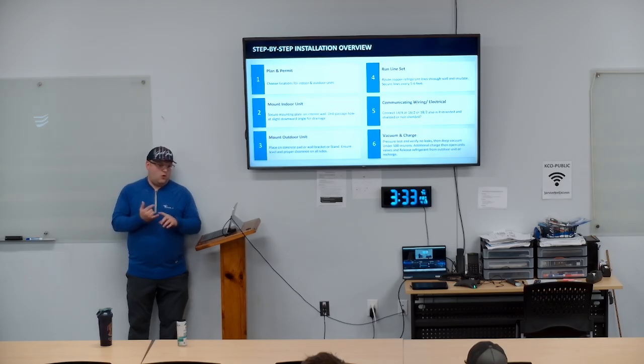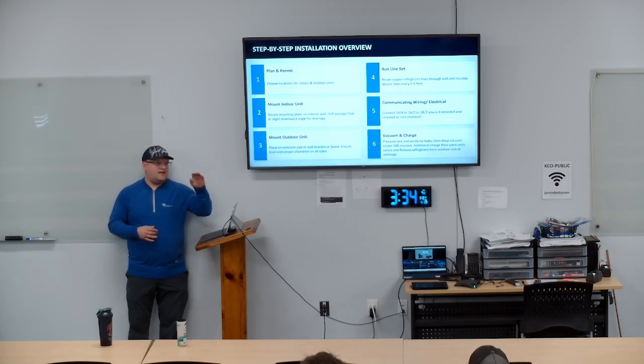The reason is because number 1 and number 2 of that, or S1, S2, L1, L2, those are the high voltage coming in to the unit. Number 3 is a variable DC signal that's running our communication. So the reason we like to run that is because electricians break wires and put disconnects on indoor units and they break that communication wire. And I can tell you, I've had to pull a million more wires because he ran all this and broke it right there and it wouldn't work. And they're like, yeah, rerun the wire. That's what the manufacturer says. Yeah, you can't break that, rerun it, and we're leaving. And it's like, okay, so we're kind of screwed.